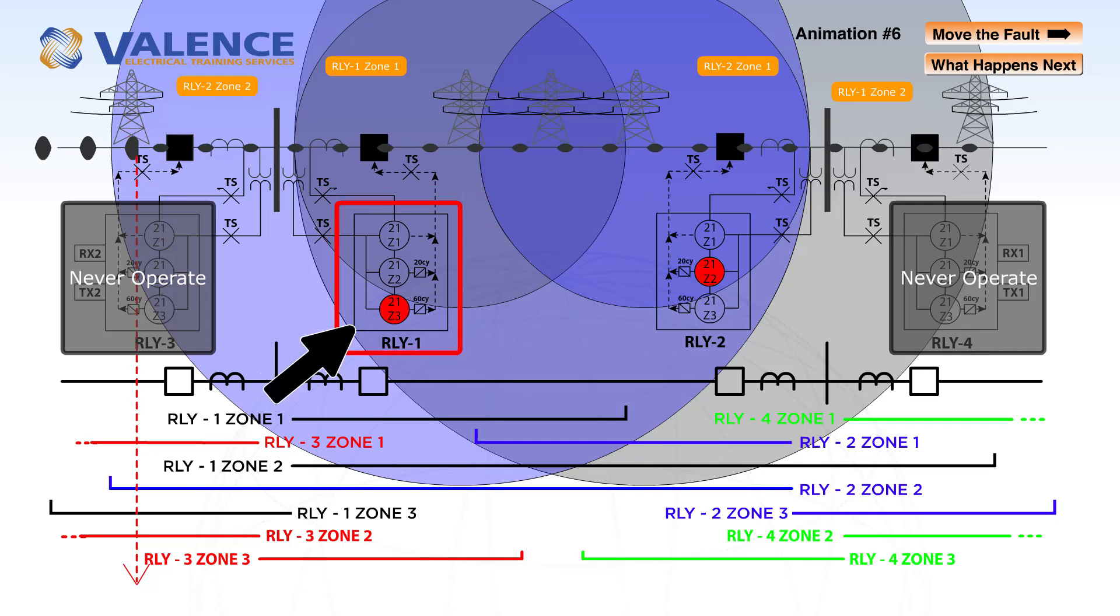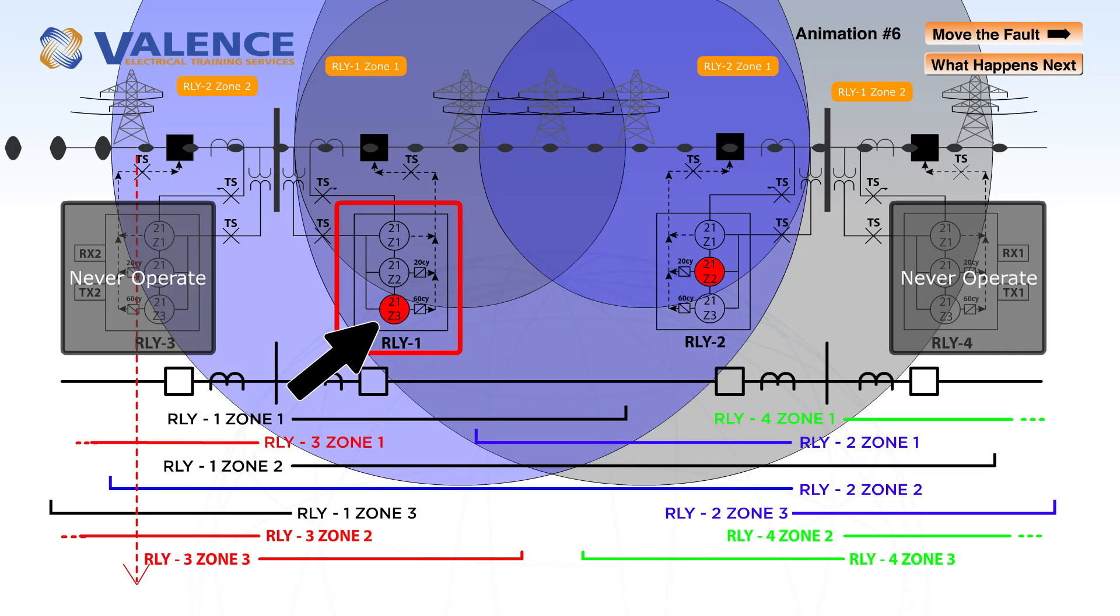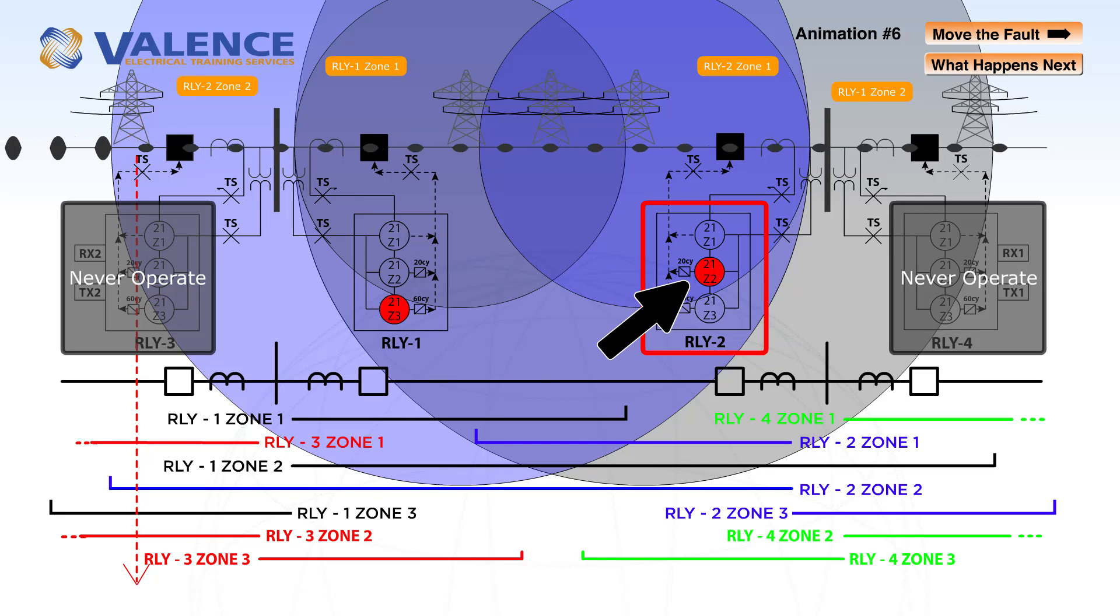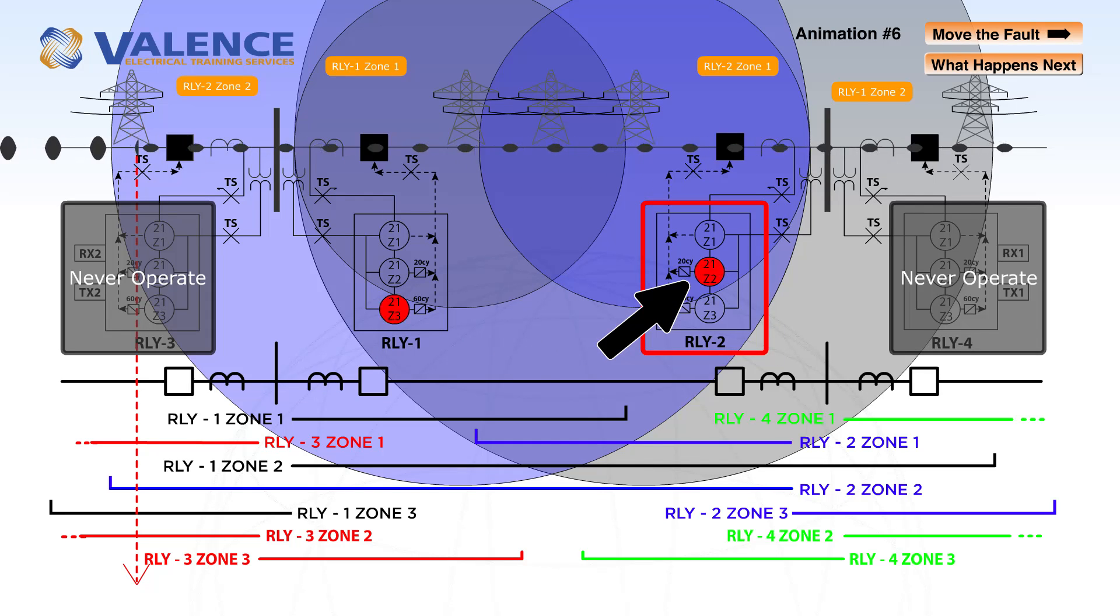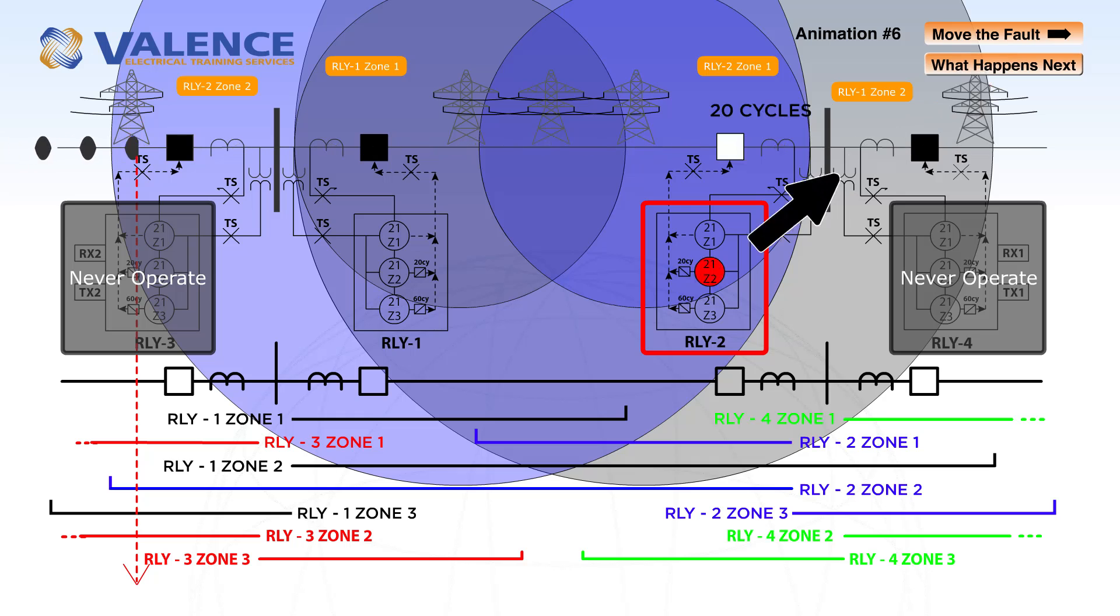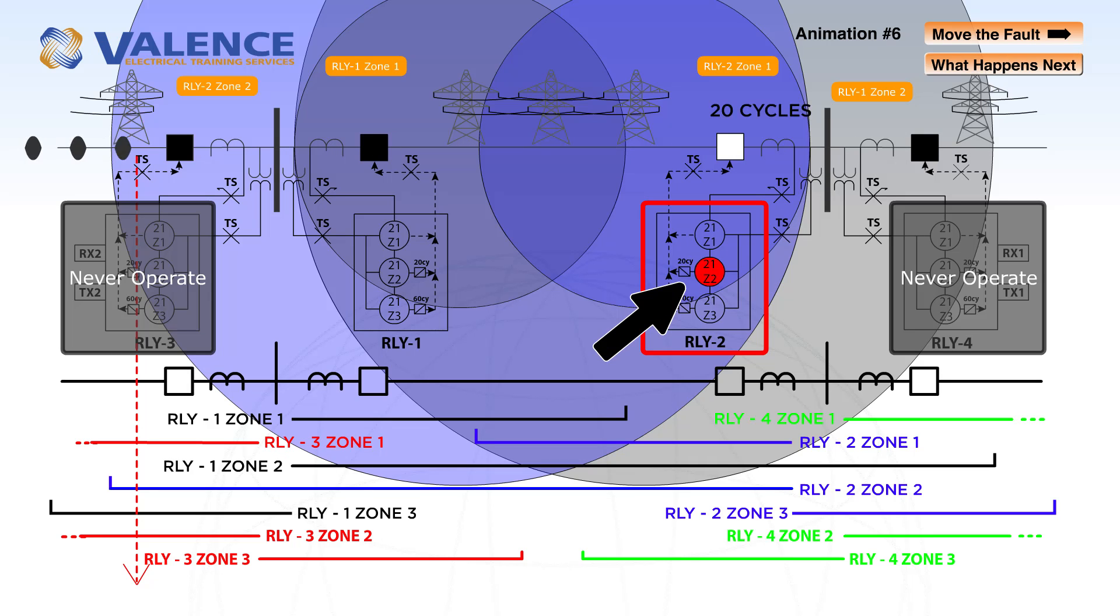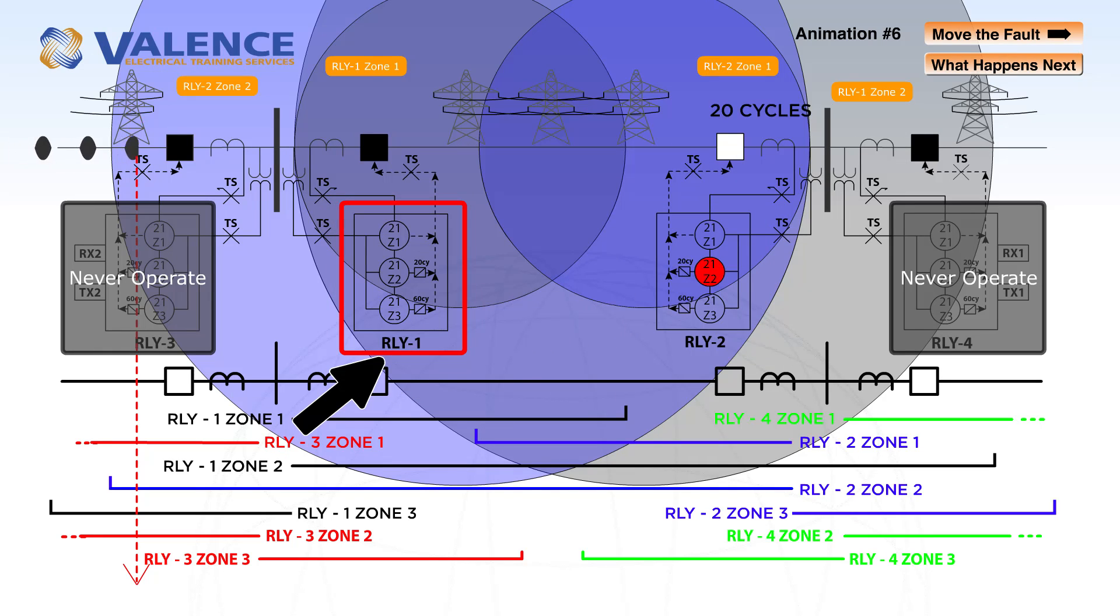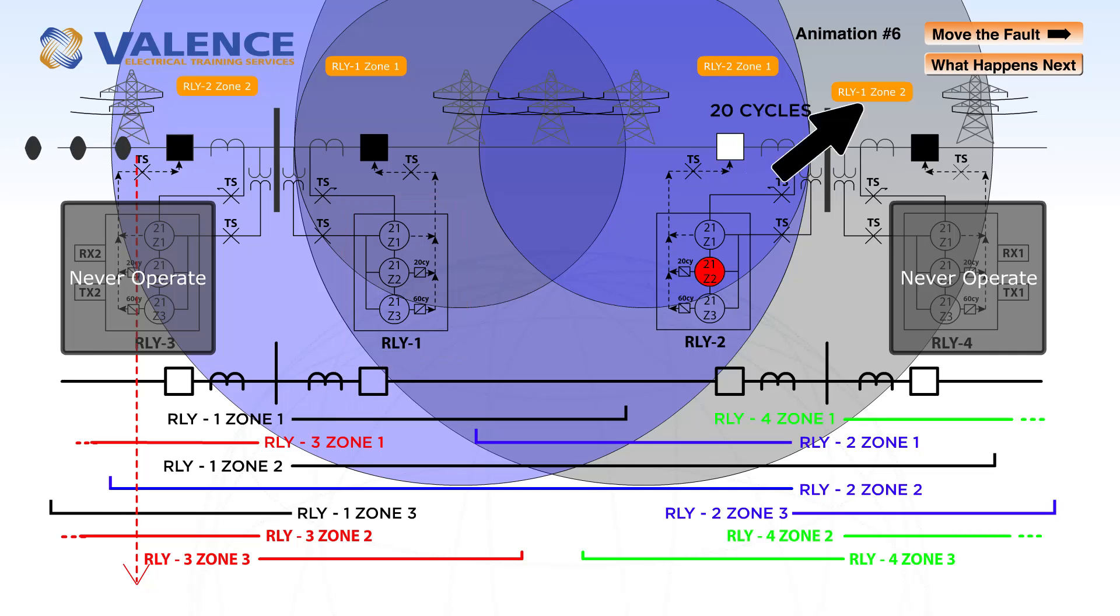Relay 1 zone 3 has a 60 cycle time delay, and relay 2 zone 2 has a 20 cycle time delay. So relay 2 will operate first and isolate the fault. Relay 1 does not get a chance to operate at all.